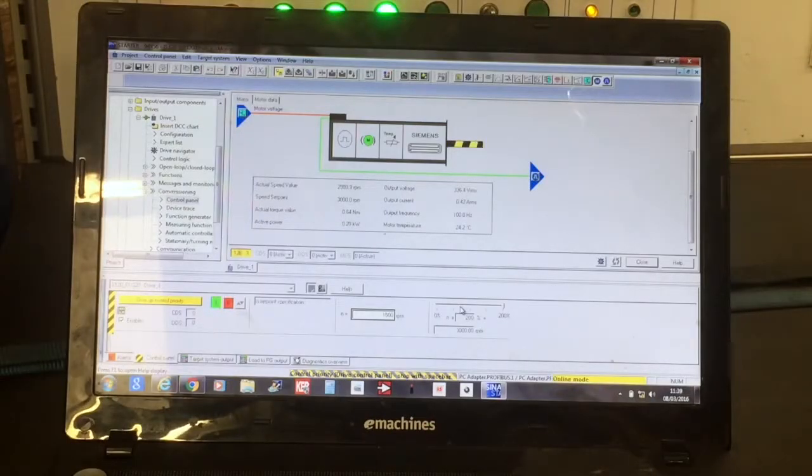The Siemens drive is operating the motor and here is the control centre on the laptop. The pictorial shows the motor operating. We are running at 3000 RPM. The motor is currently giving an output power of 0.22 kilowatts, which is 0.63 newton metres, and the motor temperature currently is 24.6 degrees C.